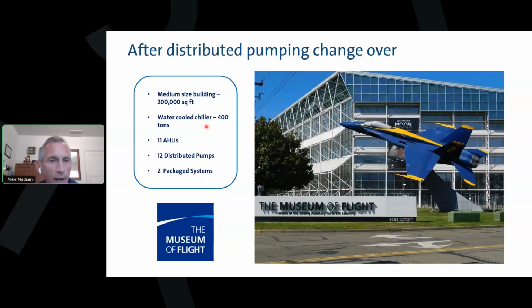They were putting in some new air handlers, a new chiller, and they heard about distributed pumping, and they said, we'd like to do a distributed pumping approach in this museum. Sort of a medium building, 200,000 square feet. The chiller was a 400-ton chiller. They have 11 air handler units. So we converted the system to distributed pumping.